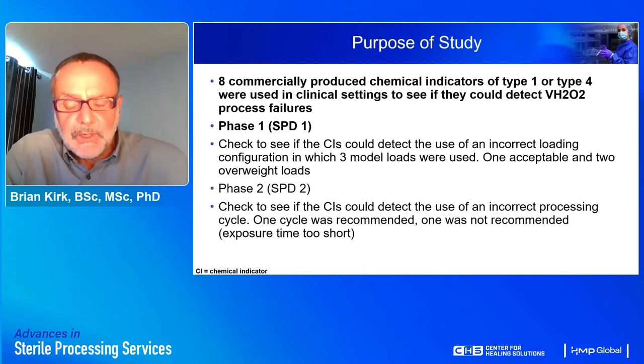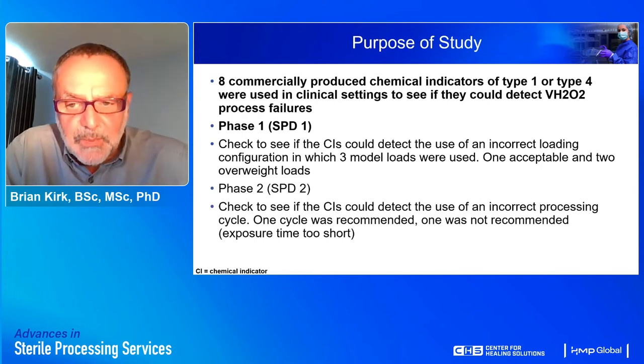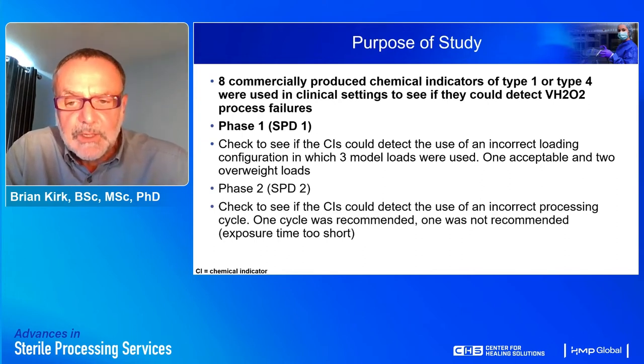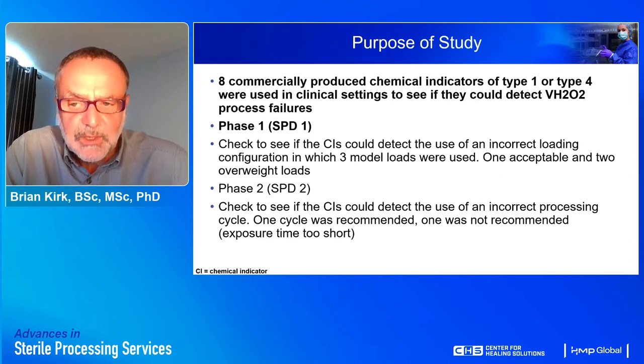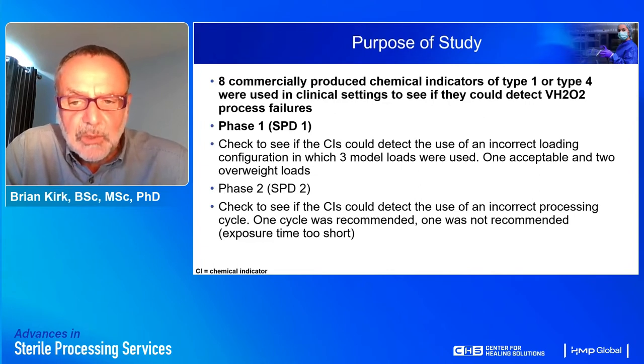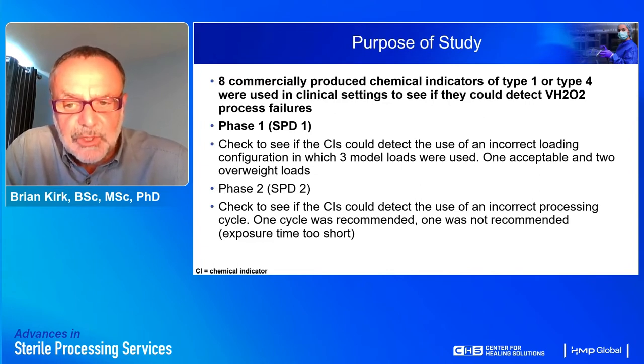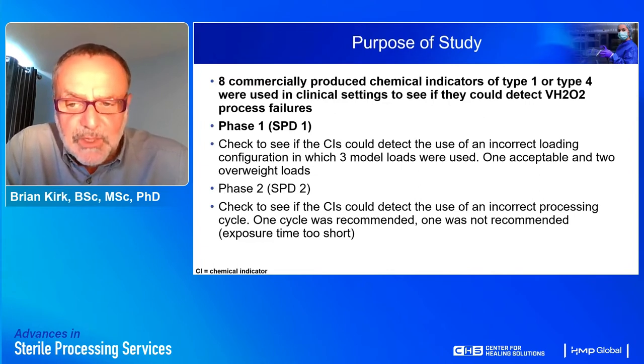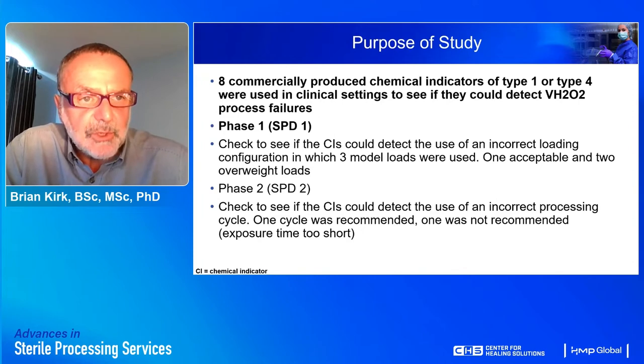In phase two of the study, at the second SPD, tests were carried out to see if the CIs could detect the use of an incorrect processing cycle. A standard load was employed, processed according to its instructions, and then in a process which was too short.